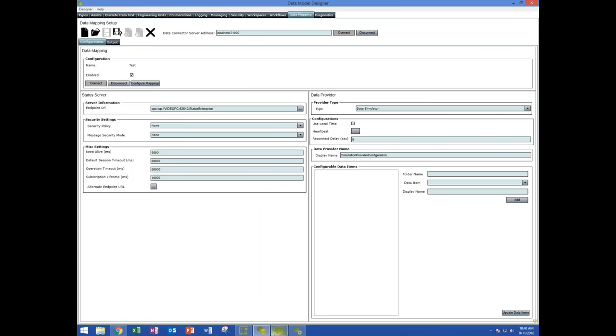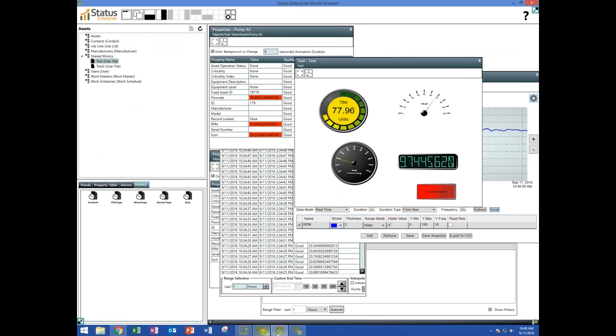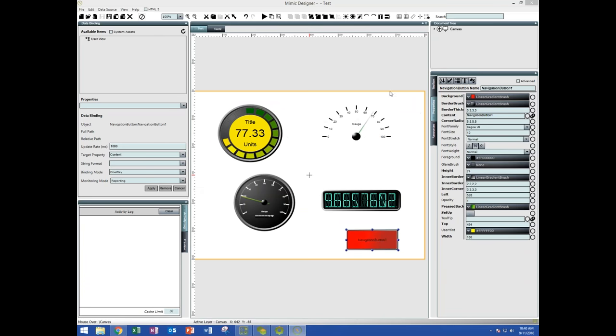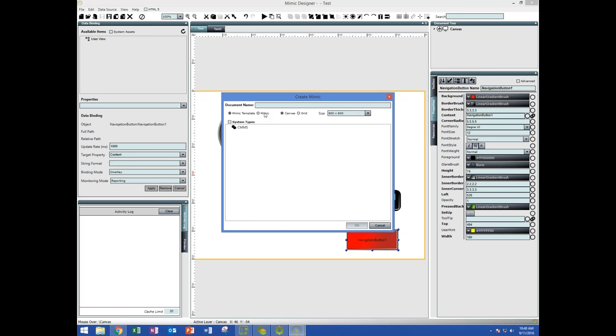There's one thing I'd like to point out in the mimic designer. When we create a mimic, we have chosen 'regular mimic,' but we can also create a mimic template. A mimic template is created for a type of thing, not a specific thing. I can create a single mimic for a pump type, and if I have 500 pumps in my system, I can use that one mimic with every single one of those pumps — I don't have to create multiple graphics for each pump. This can save huge amounts of time.